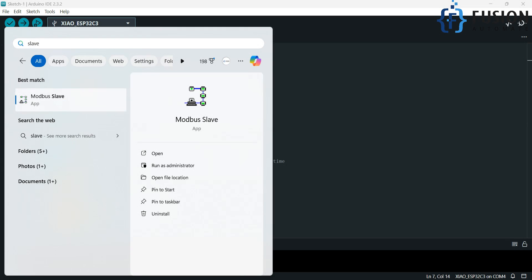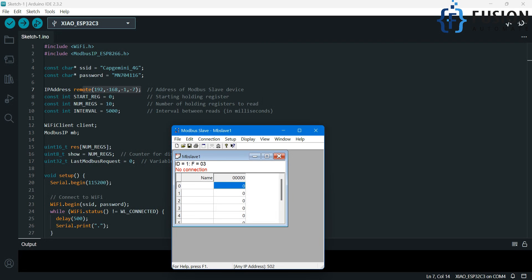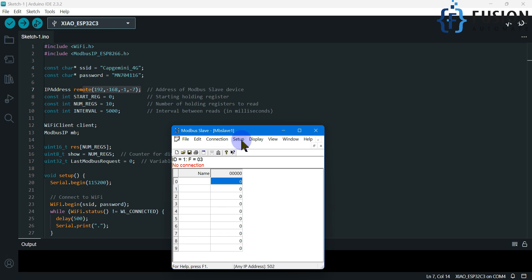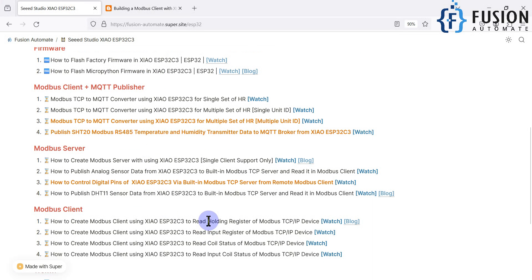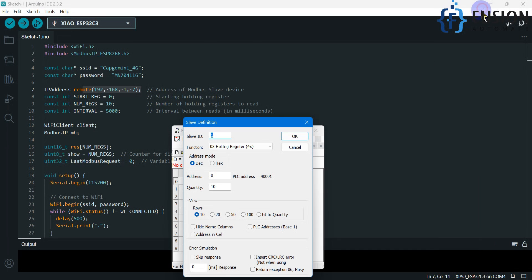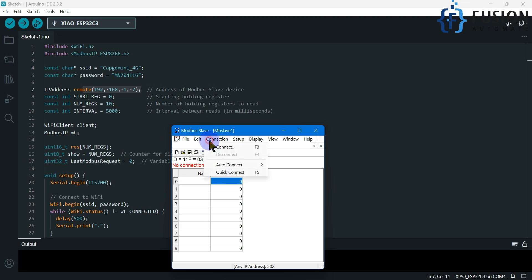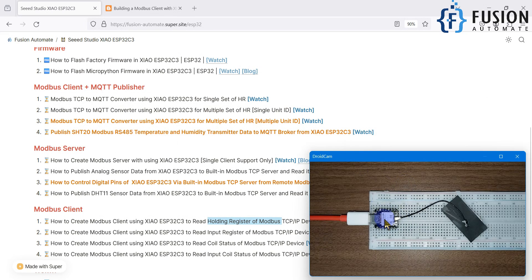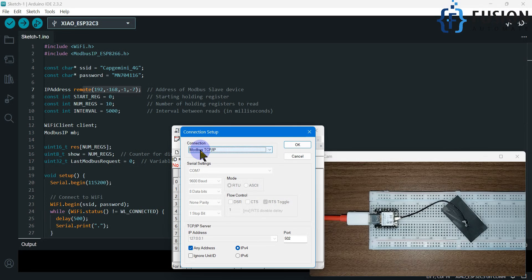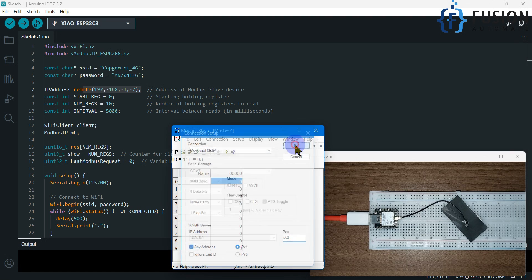Let me run the Modbus TCP device. We will open the Modbus Slave software — I have already uploaded videos on how to download and use it. You can click on Setup, go to Slave Definition, and since our target is to read the holding registers, we will select the holding register and set the quantity to 10. Then go to Connection, click Connect, and select the Modbus TCP/IP connection type. The port number is 502 — press OK.